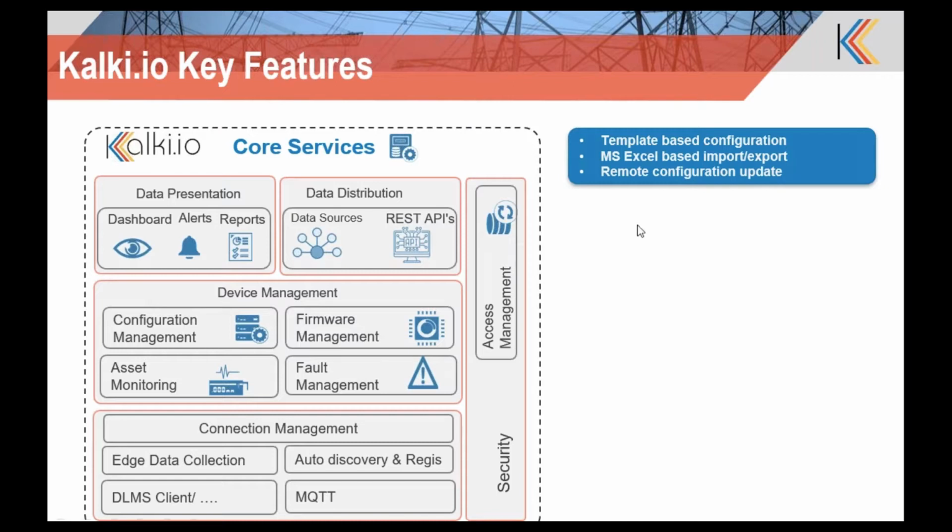So let's talk about configuration management, some few concepts which we have introduced in Kalki.io. It's template-based configuration, which means that in case of DLMS meters, there's an extensive list of templates available in the platform, depending upon the make and model of the meter, as well as the compliance standards like the Indian compliance standard or TNB or SEC, etc. So all the compliance standard templates are available. You can use any of these templates, instantiate the number of meters you want to connect to, configure those meters, and directly connect with the meters then and there from the head end.